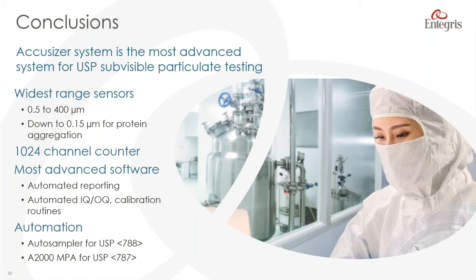So that is a summary of the newest instrumentation and automation available from Entegris for performing USP subvisible particulate testing. Some of the ways in which these systems are unique is first, with the Accusizer using the LE400 sensor, we have this wide dynamic range, measuring from 0.5 to 400 microns, and we can actually get down to 0.15 microns if we need to for testing protein aggregation.